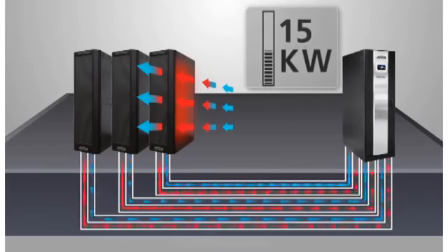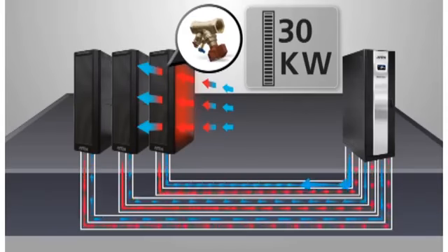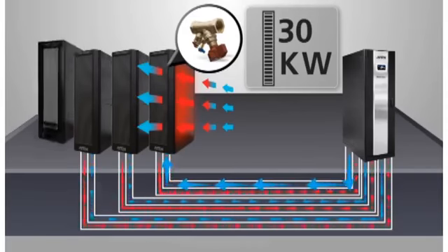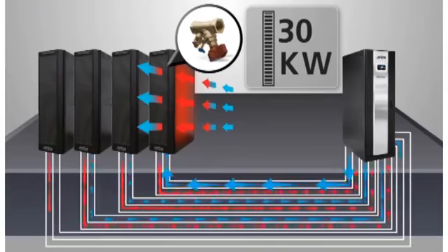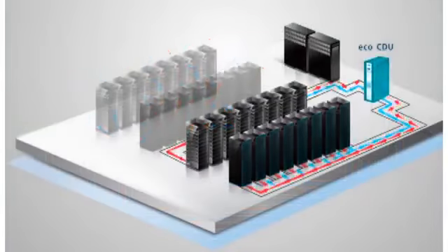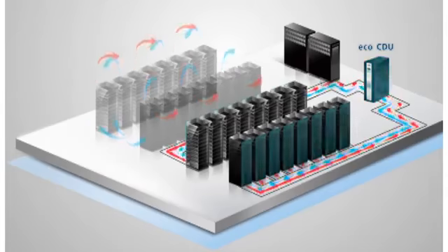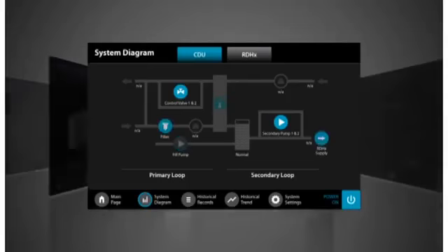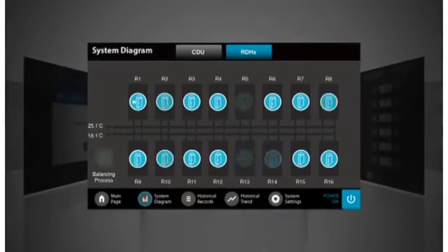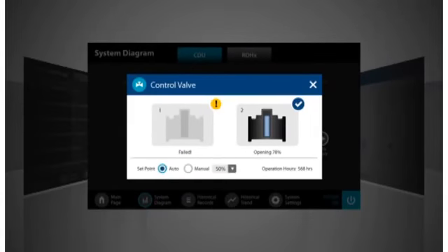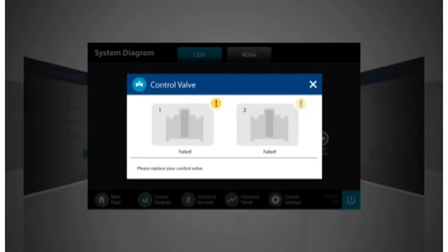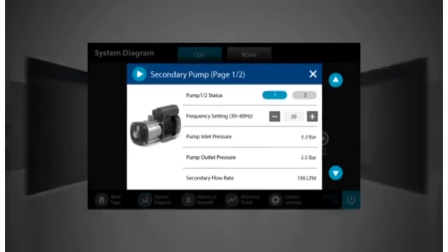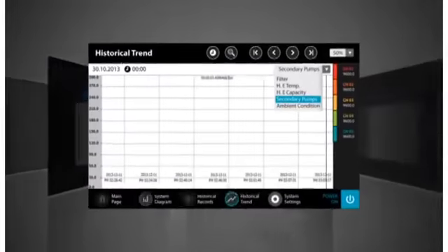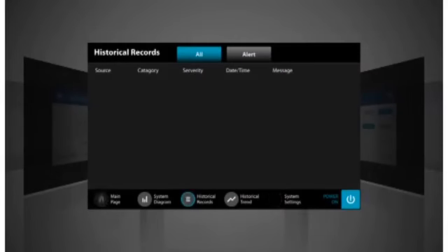To add server racks, simply enhance the cooling system settings and add rear door heat exchangers to the new racks. The RDHX mounts easily to the rear of any standard server rack and uses almost no space. The CDU has an interface that provides A. A simple touchscreen menu. B. Precise CDU and RDHX status information. C. Diagrams that demonstrate the operation and provide settings for each loop, such as the control valve, heat exchanger, and secondary pump. D. CDU historical trends and event logs.